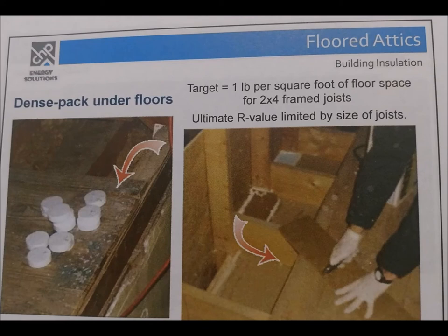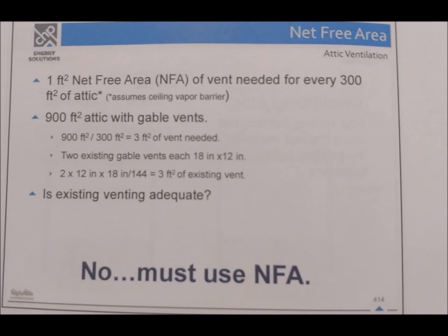Floored attics: Dense pack under floors — the target is one pound per square foot of floor space for a 2×4 frame joist. Ultimate R-value is limited by the size of the joist. Net free area (NFA): one square foot of NFA vent needed for every 300 square feet of attic, assuming a ceiling vapor barrier. Example — 900 sq ft attic with gable vents: 900 divided by 300 equals 3 sq ft of vent needed. Two existing gable vents each 18×12 inches: 2 times 216 equals 432 sq in equals 3 sq ft of existing vent. Is existing ventilation adequate? No — must add NFA.